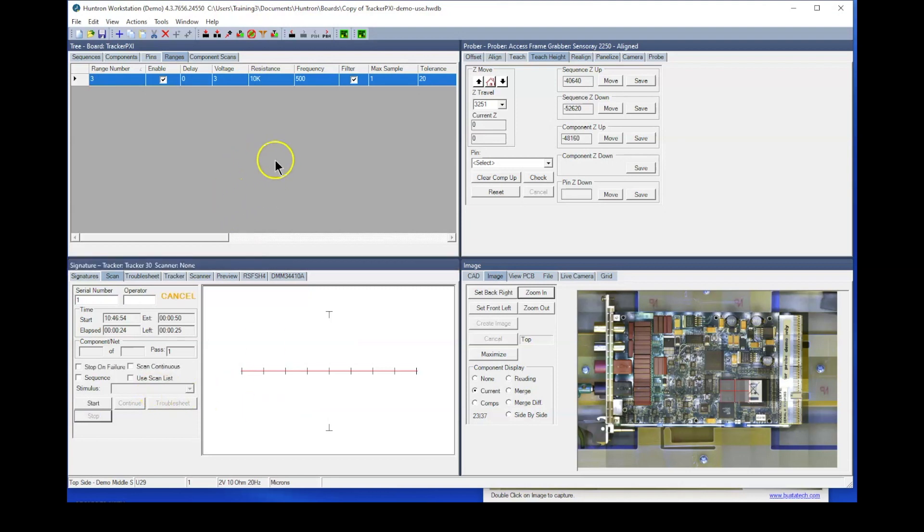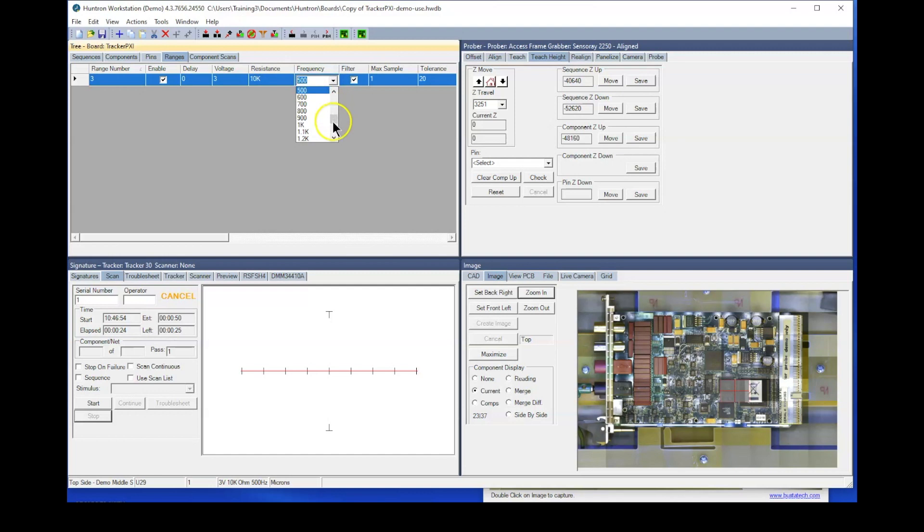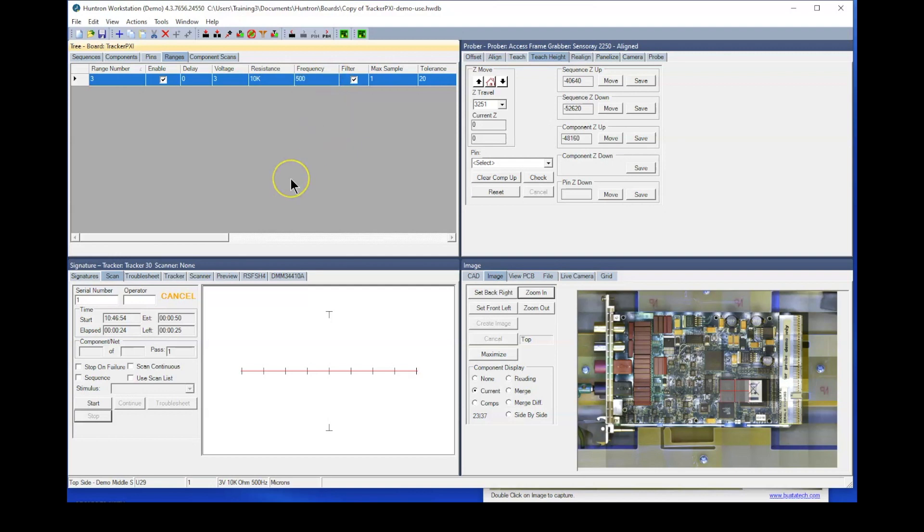We have had users report that changing the frequency from low frequencies, such as like 100 hertz, up to maybe possibly 500 hertz also decreased test times. Of course, the reason being is that with a faster frequency, that means that again, the probe does not have to spend so much time sitting on that pin. And therefore, it will decrease your test time. However, I think that would only have a benefit if you're testing hundreds and thousands of pins versus just 10 or 20 pins.